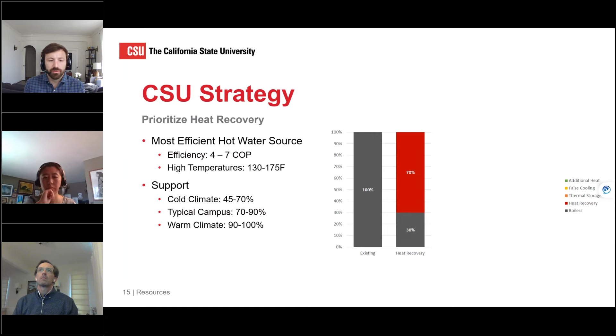Another key CSU strategy is to prioritize heat recovery. Most campuses have central chilled water, central heating hot water, or steam systems. Heat recovery is the most efficient way of producing hot water, with efficiencies between 7 and 4 COP depending on the temperatures. Heat recovery chillers can also supply up to 170, 175 degrees, which is critical where a lot of campuses were designed around high temperature heating hot water systems, up to 250, 300 degrees. And this can be supported in cold, typical, and warm climates. With the typical CSU campus, we see around 70% of the overall campus's central heating can be provided from heat recovery.